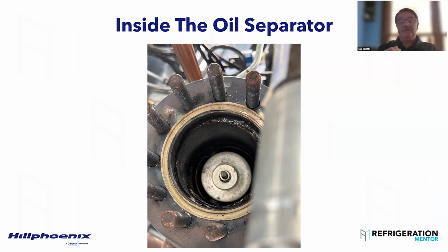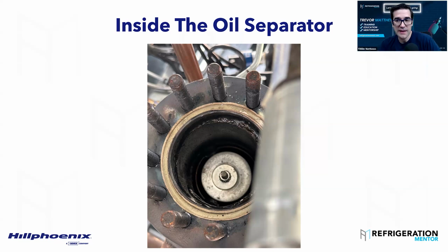One of the things you want to do, once you get that one done, is don't turn the switch off, because I've noticed in the past where we isolate number one, turn the switch off, go to fill number two, and then number one starts to get low again. So leave the switch on, let it work while we're sitting there idle. Fill up your number two medium temp, number three, number four, however many medium temp compressors. Fill the reservoir as required for oil. Then you'll start with your low temp and fill all your low temp compressors up. We want to see the switches come on and shut the flow off. Yeah, that's amazing, right? And I love that.